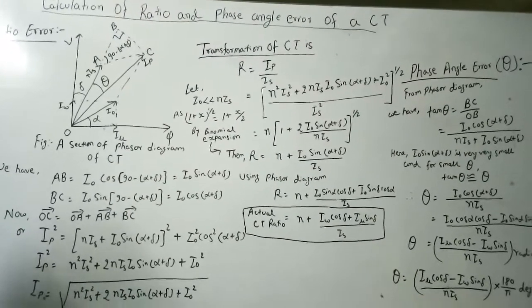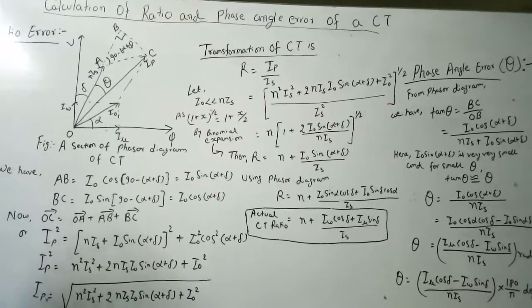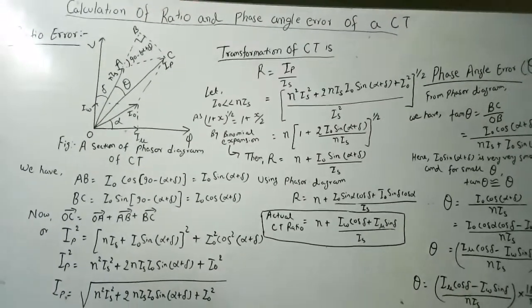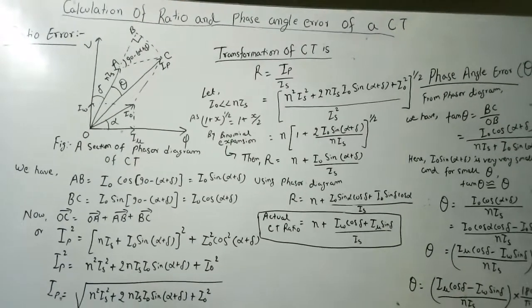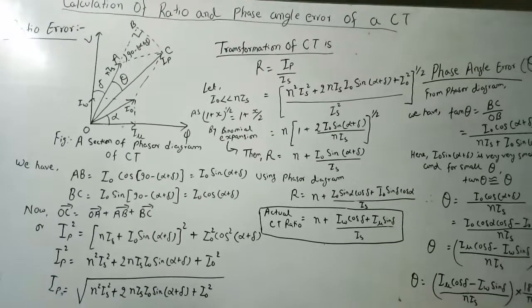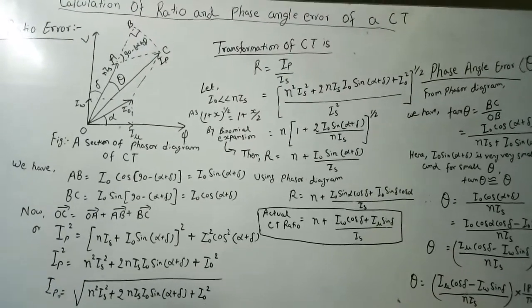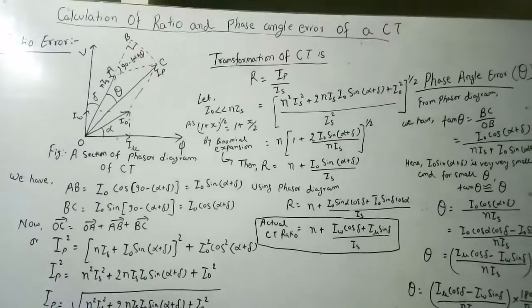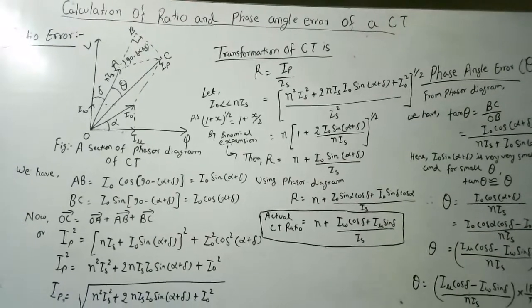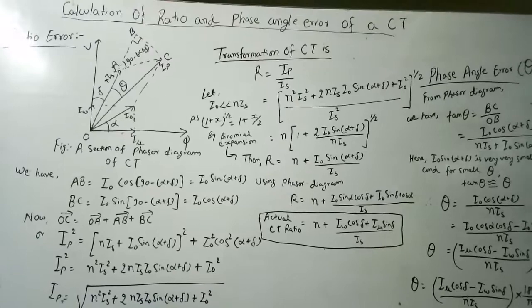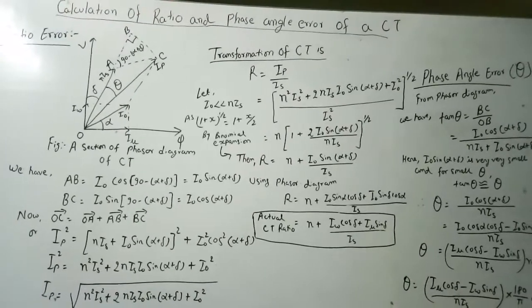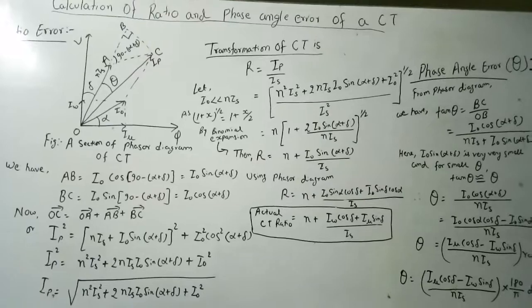In the last lecture, we also dealt with what is ratio error. It is the ratio of the difference between nominal ratio minus actual ratio, upon actual ratio. And phase angle error is defined as the angle by which the secondary current phasor, when reversed, differs in phase from the primary current.